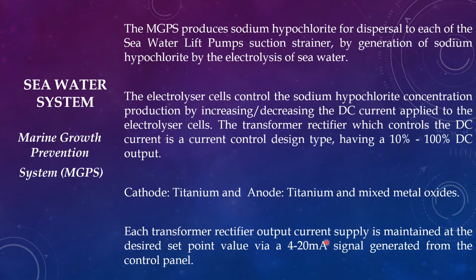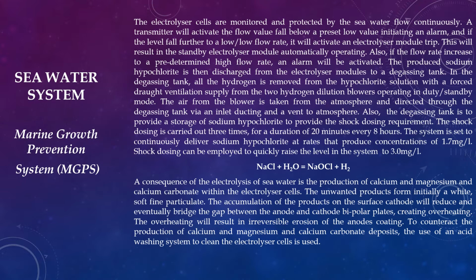Each transformer rectifier output current supply is maintained at the desired set point value via a 4 to 20 milliamp signal generated from the control panel to the electrolyzer cell. The electrolyzer cells are monitored and protected by the seawater flow continuously. A transmitter will activate if the flow falls below a preset low value, initiating an alarm, and if the flow falls further to a low-low flow rate, it will activate an electrolyzer module trip.